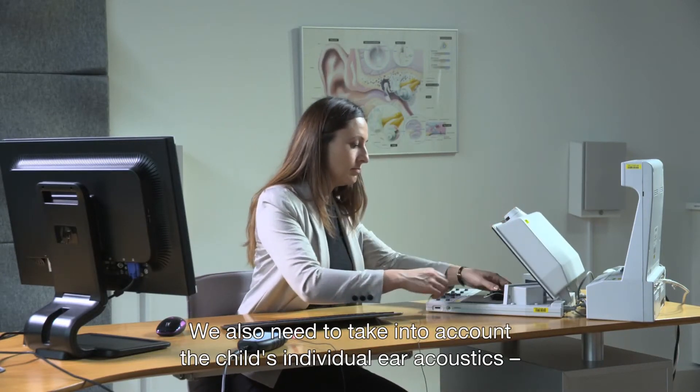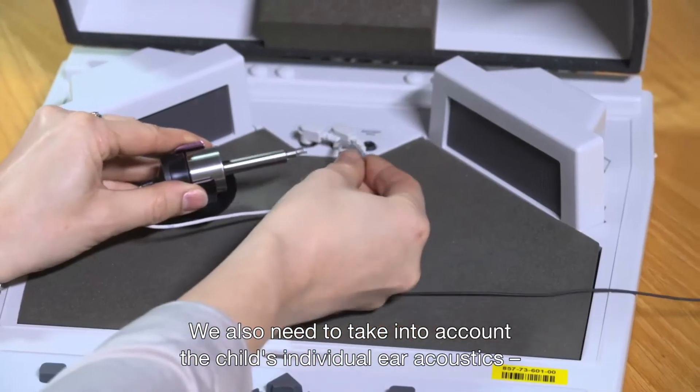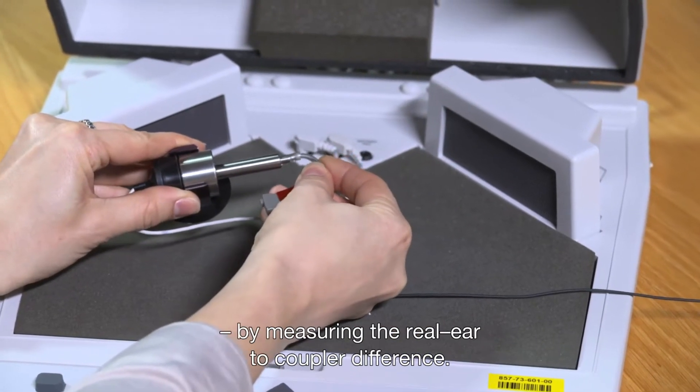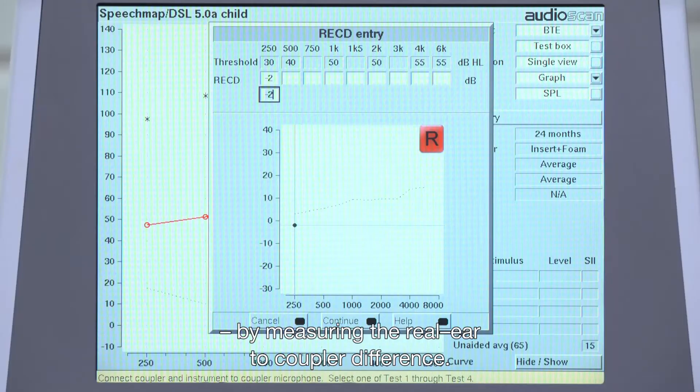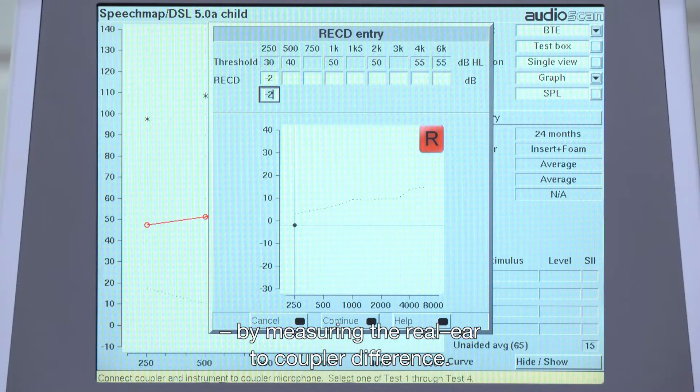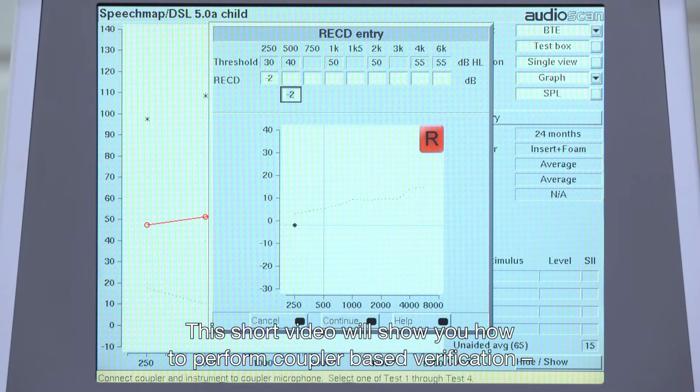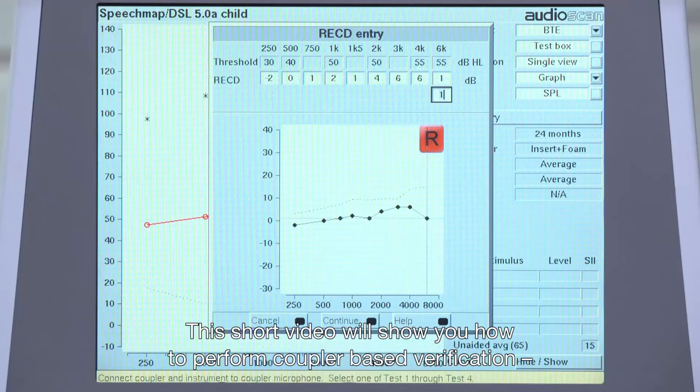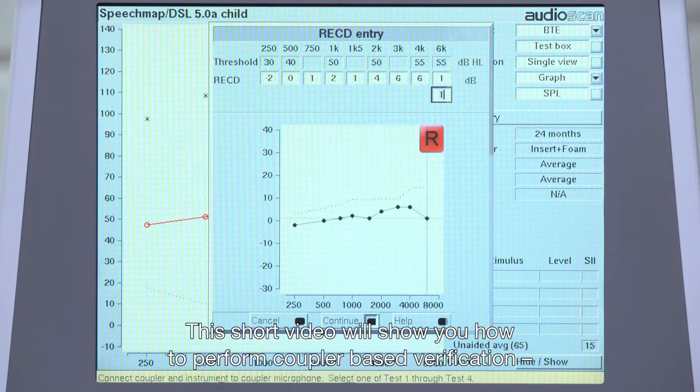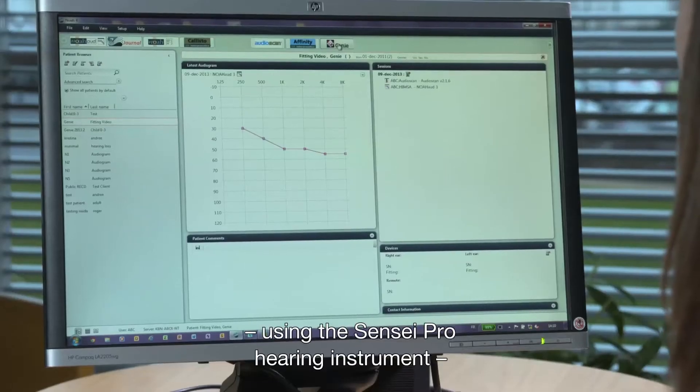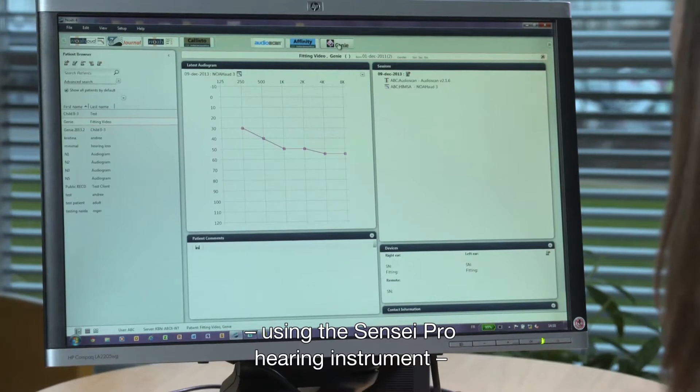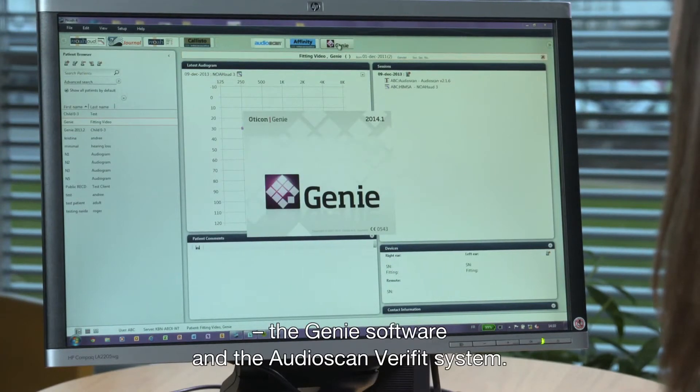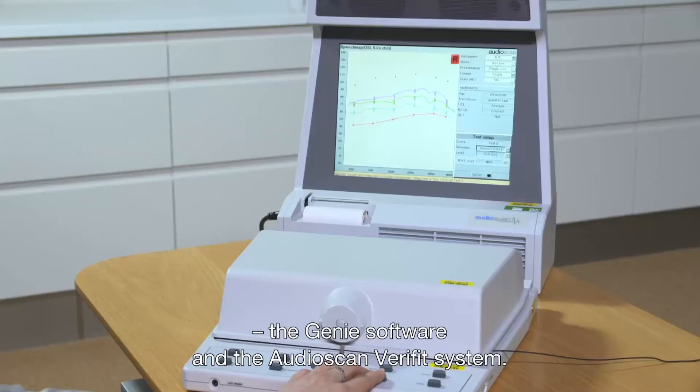We also need to take into account the child's individual ear acoustics by measuring the real ear to coupler difference. This short video will show you how to perform coupler-based verification using the Sensei Pro hearing instrument, the Genie software, and the AudioScan Verifit system.